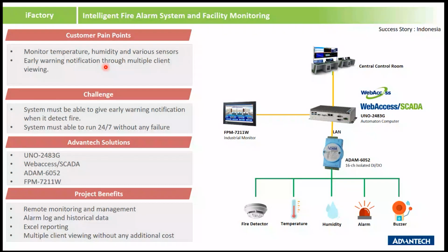They want to have early detection. So the challenges are: the system must be able to give early warning notification when it detects fire, and it must be able to run 24/7 without any failure. By using our DAQ devices here, it is very reliable. Also, by using LAN, we're able to give early warning detection with no delay, unlike wireless which might have some delay. With wired, you get real-time data monitoring.